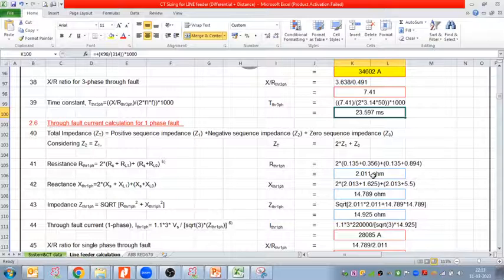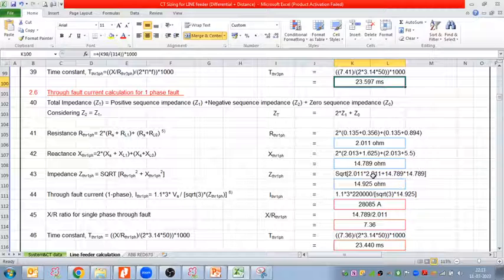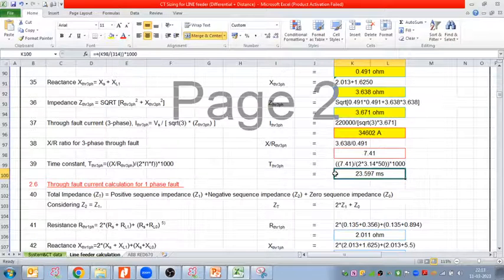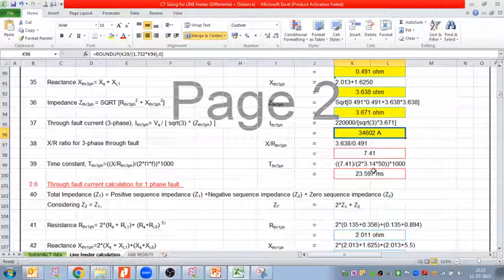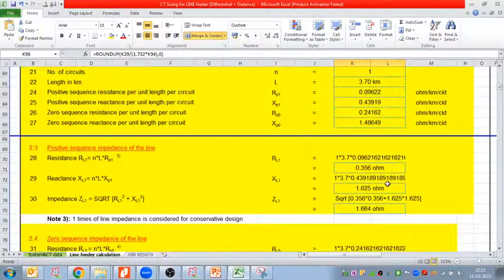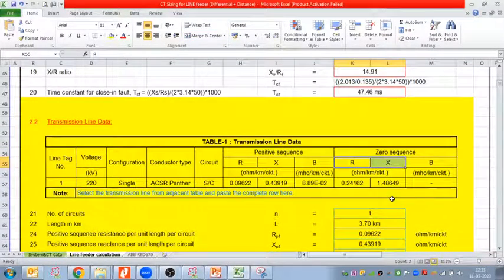Now one more thing we need to check: if any fault is happening, there could be a single phase to ground fault that may happen. This is one fault, where any conductor is broken and comes onto the ground. The most severe fault would be the three phase fault, where all the three phases are shorted together. So this fault that we calculated is the three phase fault. If we want to calculate the single phase fault, whatever zero sequence resistance and reactance you are getting, you have to use that, and based on that we need to calculate the single phase fault value.